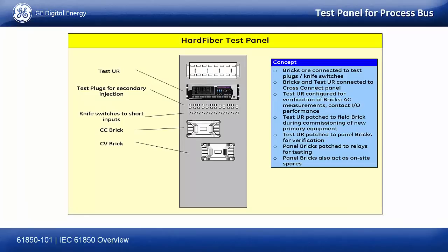And if I want to do testing in the field, I can build a test panel for process bus where I have spare bricks. I can connect any relay to any brick in the field. I connect these spare bricks to any relay for testing and so on. They also become in-field spares that I can use, and I can patch the stations.